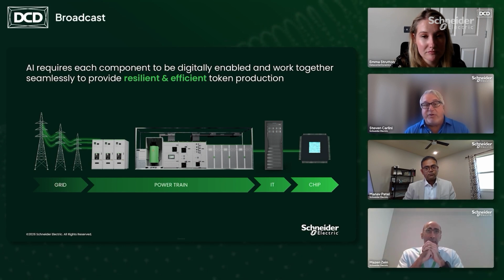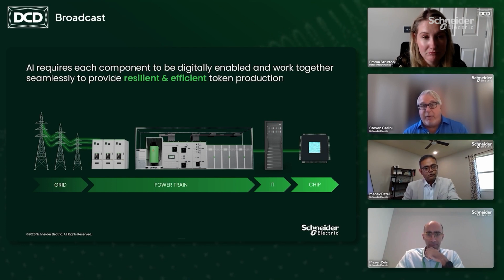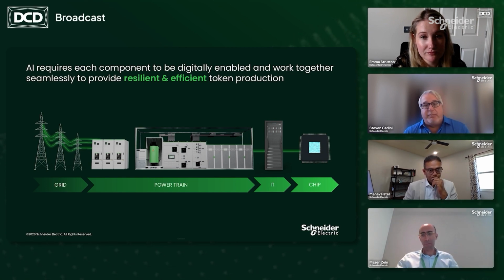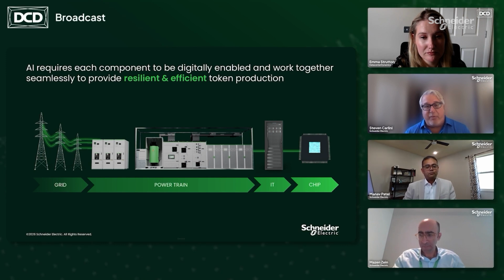Within that power train, it's continuous and only as reliable or available as its weakest component. Starting at medium voltage, you see switch gear, breakers, busway, transformers, UPS systems, power distribution units - all operating in one continuous power train. We manage every point of that power train: monitoring breakers to see if they're getting close to capacity or could trip, monitoring transformers to see if they have rising heat and could fail. It's a very sophisticated and resilient system.